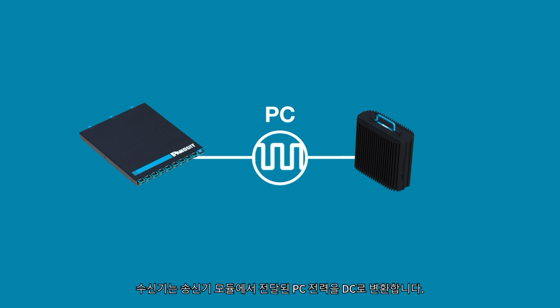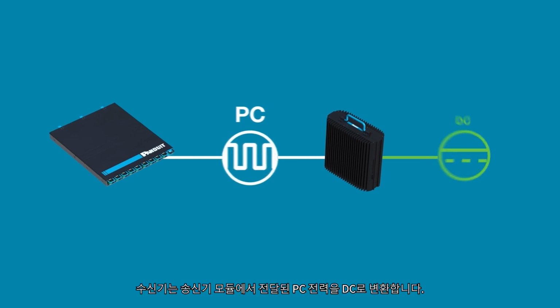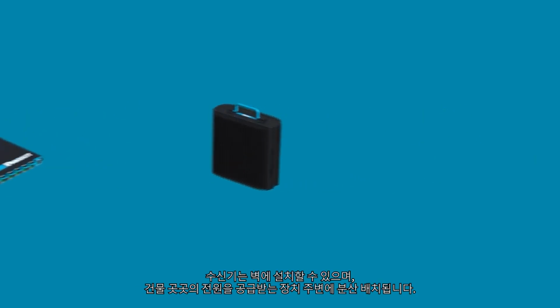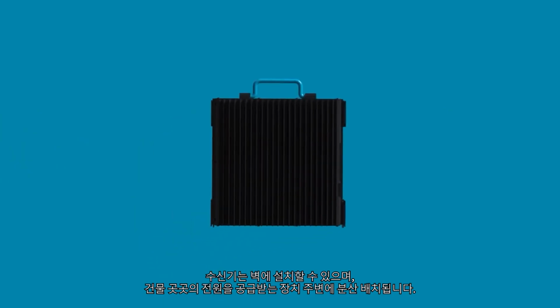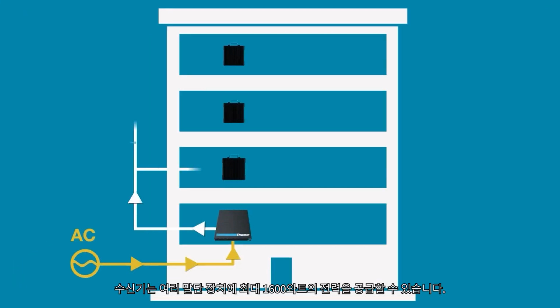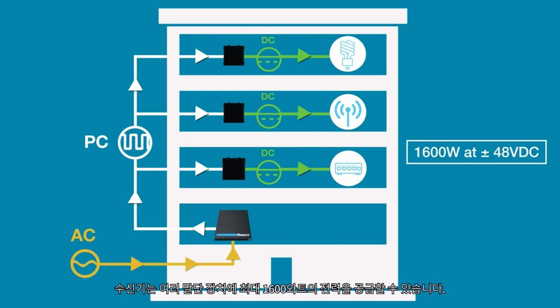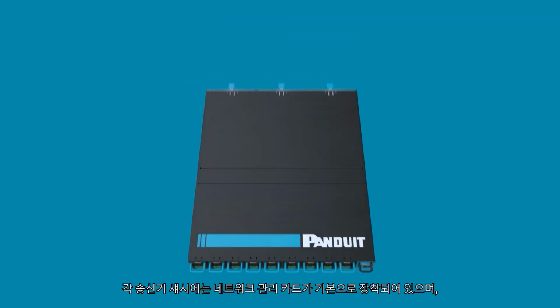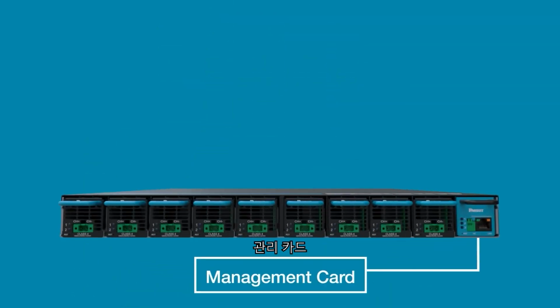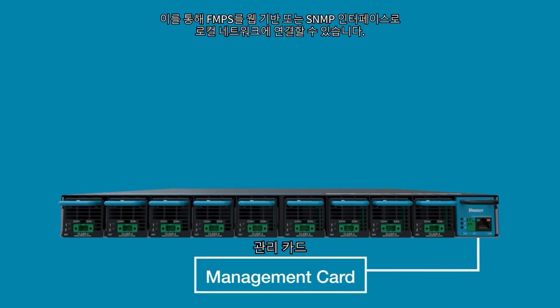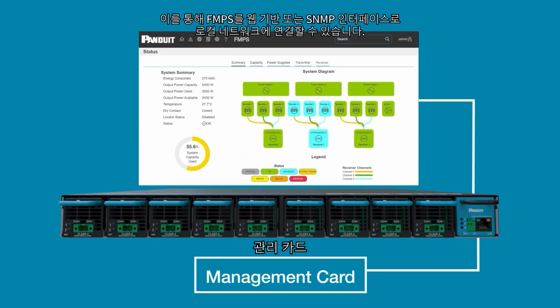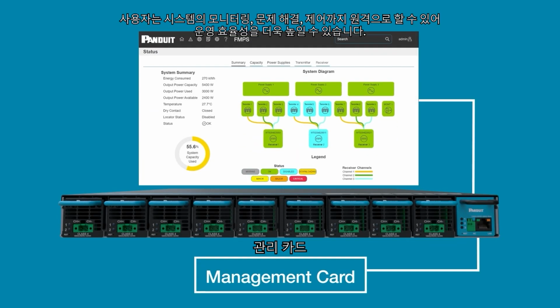A receiver takes PC power from a transmitter module and converts it to DC. Receivers are wall-mountable, distributed around the building near powered devices. A receiver can deliver up to 1,600 watts to power multiple end devices. Each transmitter chassis comes with a pre-installed network management card that connects the FMPS to your local network. Through a web-based or SNMP interface, users can monitor, troubleshoot, and control the system remotely for improved operational efficiency.